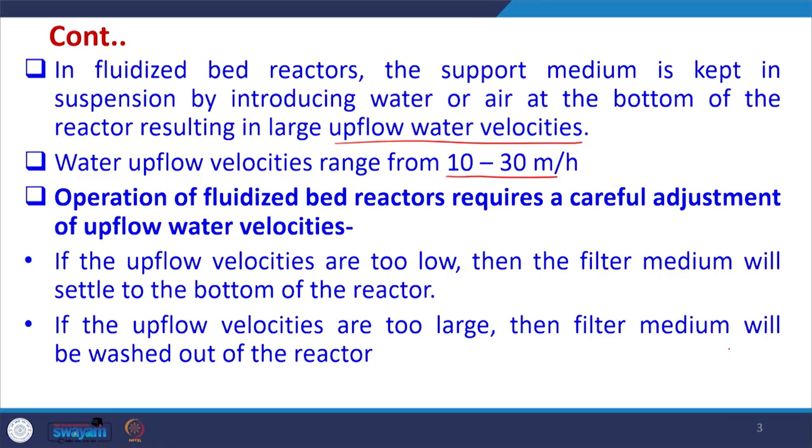Operation of a fluidized bed reactor requires careful adjustment of the upflow water velocity, which is the most important parameter. If the upflow velocities are too low, the filter medium will settle to the bottom of the reactor — the bioparticles will settle down. If the upflow velocities are too large, the bioparticles will be washed out of the reactor. So we have to decide the upflow water velocities very carefully.